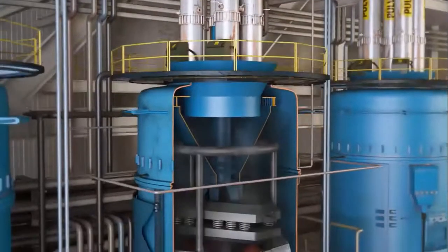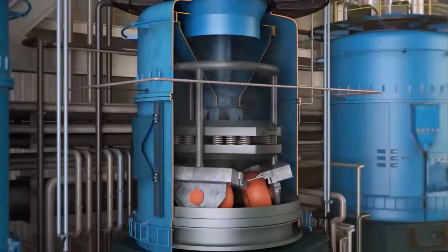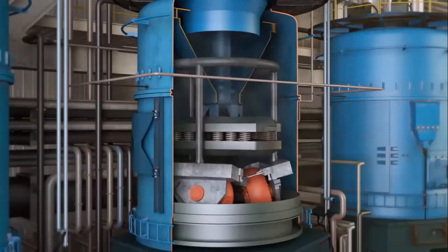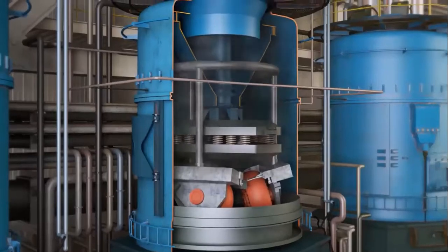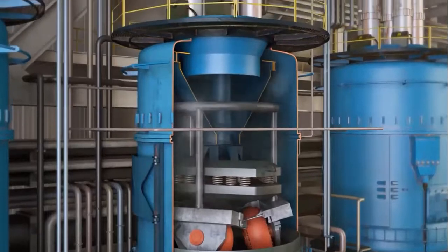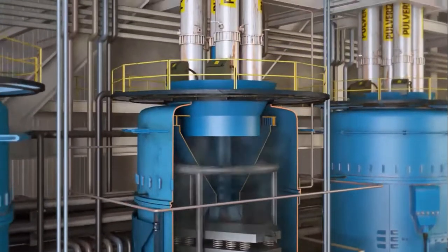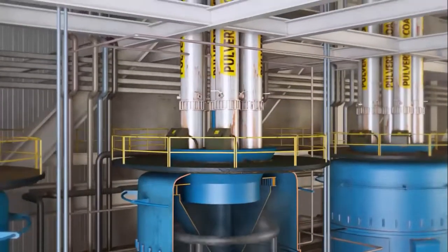Inside the pulverizer, coal falls onto a large rotating bowl, where it is continuously crushed by three large grinding wheels until it becomes the consistency of baby powder. Once the coal is a fine powder, it falls off the grinding bowl and is carried by warm primary air, maintained at 140 degrees Fahrenheit inside the pulverizer, to the boiler through 8 burner lines.